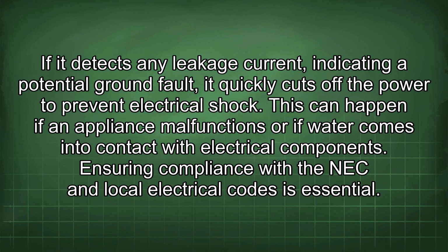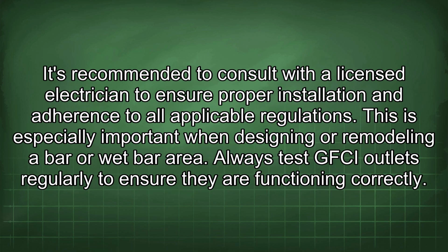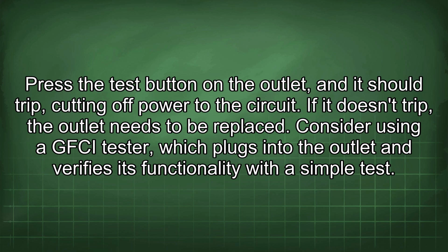Ensuring compliance with NEC and local electrical codes is essential. It's recommended to consult with a licensed electrician to ensure proper installation and adherence to all applicable regulations. This is especially important when designing or remodeling a bar or wet bar area. Always test GFCI outlets regularly to ensure they are functioning correctly. Press the test button on the outlet, and it should trip, cutting off power to the circuit. If it doesn't trip, the outlet needs to be replaced.